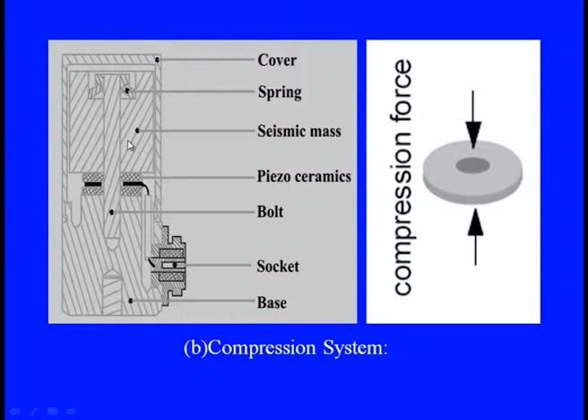And if you go to the compression design, you can see that there is clear compression on the piezoelectric material. The output cover sits with the base, and when the excitation comes and these bolts are provided, the seismic mass and the piezo ceramics are well balanced, because it can contain high compression. So compression mode accelerometers offer a simple structure. We don't have to go with different combinations of the seismic mass and the entire assembly. It has good rigidity, and because of the simplicity it is very widely available.